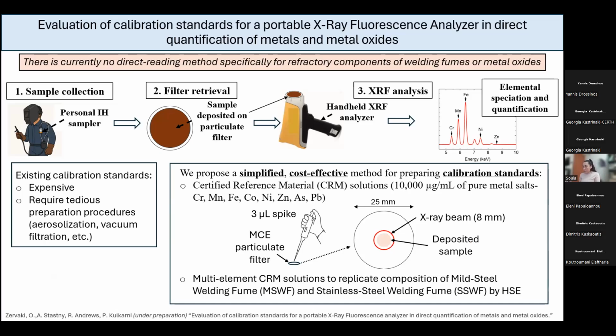standards. And how I did that: you can obtain from the market some very highly concentrated, certified reference material solutions that contain pure metal salts. You can get this for maybe $90 per sample. And you can create your own serial dilutions by using just one pipette. Very simple preparation procedure. And then you take a filter, any filter that you want to use as your substrate. I use the MCE particulate filters because they are widely used, particularly for metal detection. And I spike 3 microliters of all my solutions on the center of the filter.